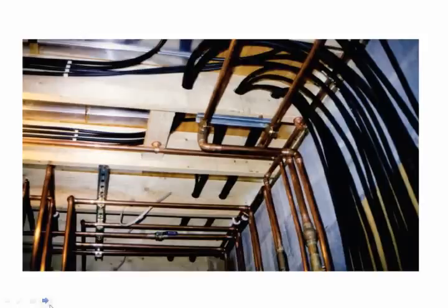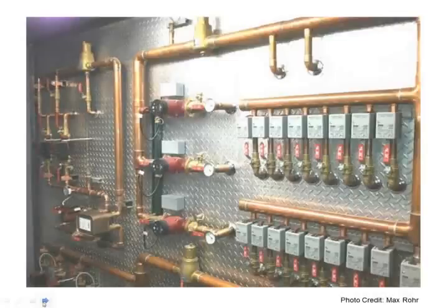They're also very efficient from the standpoint of how much electrical energy it takes to distribute that heat throughout the building. So pumps, as an example, consume significantly less energy versus a fan system, a fan doing the same thing. And that basically boils down to the properties of air. Air is compressible, and it's not so efficient to get air to move from A to B in an effective manner versus water, which is basically incompressible, and as a result, pumps can be applied, and heating or cooling our building can be done very efficiently.